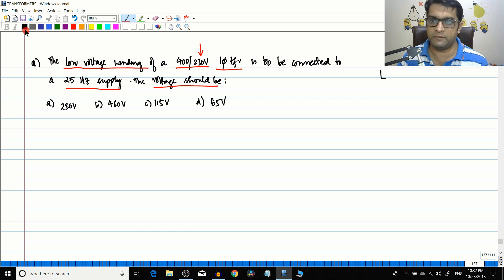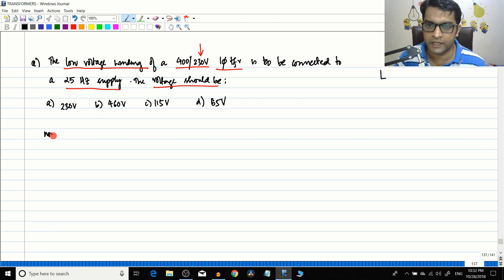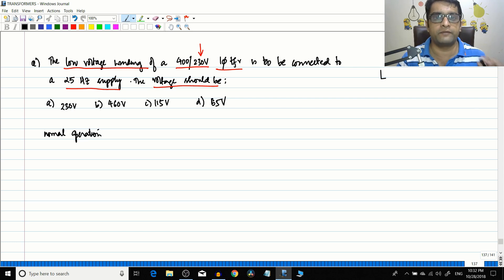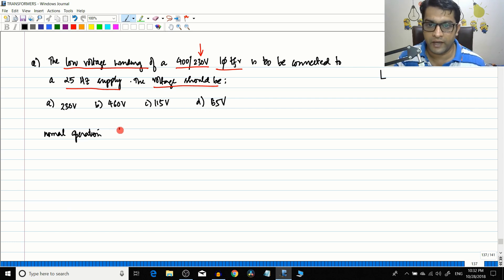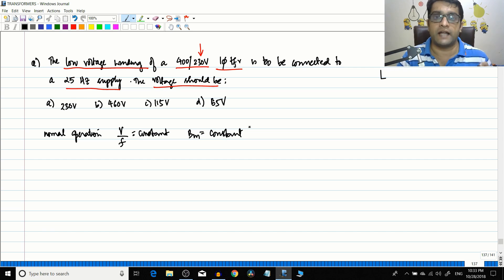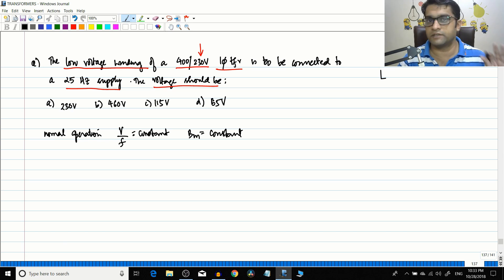They are asking what should be the voltage. Under normal operating condition, if you are trying to change the voltage or the frequency, you should always ensure that the V/f ratio is constant. V/f should be constant because if V/f is constant, naturally Bm — the maximum flux density — is also constant. That means the transformer works at its rated flux, so all the core losses are within limits and the transformer will not go into deep saturation.